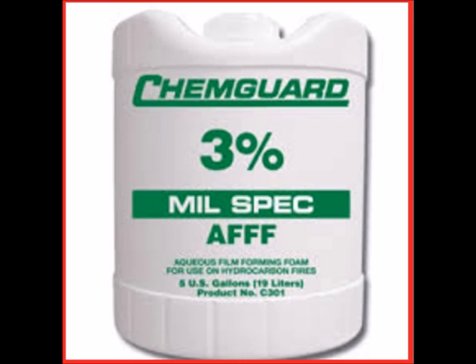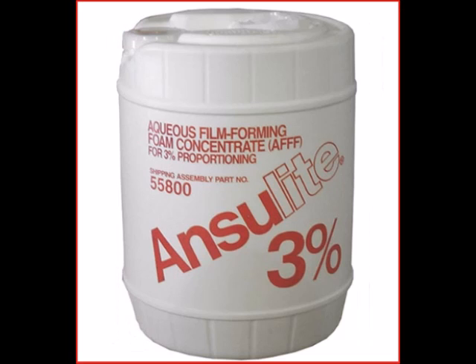In the mid-1960s, the U.S. Navy developed aqueous film-forming foam, AFFF. This synthetic foam has a low viscosity and spreads rapidly across the surface of most hydrocarbon fuels. A water film forms beneath the foam, which cools the liquid fuel, stopping the formation of flammable vapors. This provides dramatic fire knockdown, an important factor in crash-rescue firefighting.